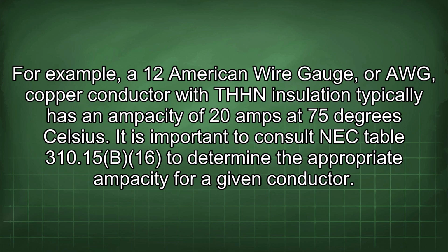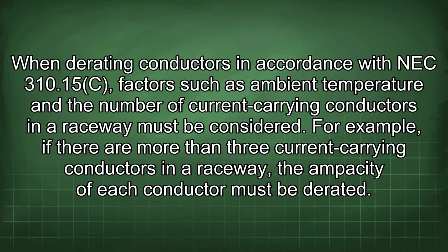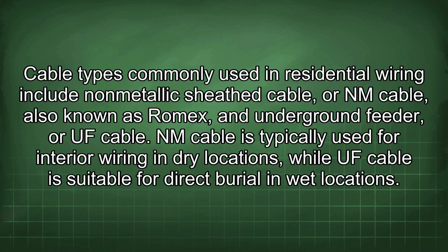It is important to consult NEC Table 310.15(B)(16) to determine the appropriate ampacity for a given conductor. When derating conductors in accordance with NEC 310.15(C), factors such as ambient temperature and the number of current-carrying conductors in a raceway must be considered. For example, if there are more than 3 current-carrying conductors in a raceway, the ampacity of each conductor must be derated. Cable types commonly used in residential wiring include non-metallic sheathed cable, or NM cable, also known as Romex, and underground feeder, or UF cable.